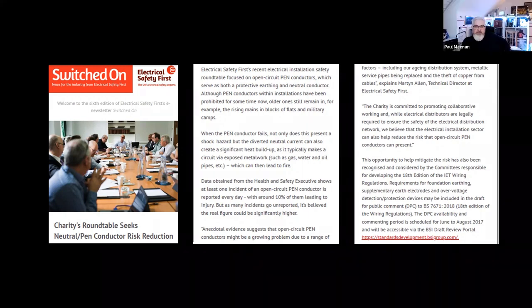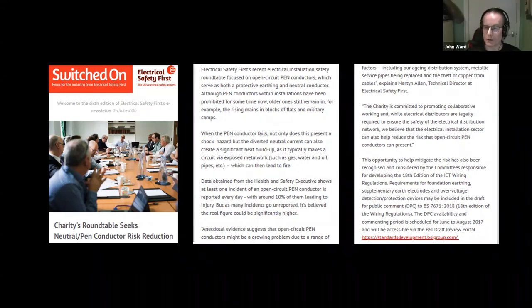Electrical Safety First's recent electrical installation safety roundtable focused on open circuit PEN conductors, which serve as a protective earthing and neutral conductor. When the PEN conductor fails, not only does it present a shock hazard, but the diverted neutral current can also create significant heat buildup, as it typically makes the circuit via exposed metalwork, which can then lead to fire. Data obtained from the Health and Safety Executive shows at least one incident of an open circuit PEN conductor is reported every day, with around 10% of them leading to injury. But as many incidents go unreported, it's believed the real figure could be significantly higher.